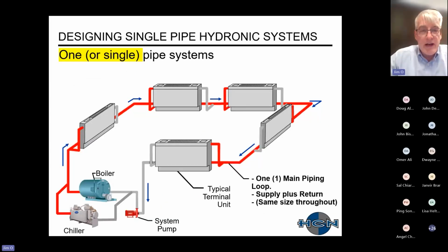So now going to a single pipe system, what you have is now just one main piping loop that travels around to each of the terminal units. So this is technically the supply as well as the return piping. You would have the same piping throughout. This is described in the ASHRAE handbook.